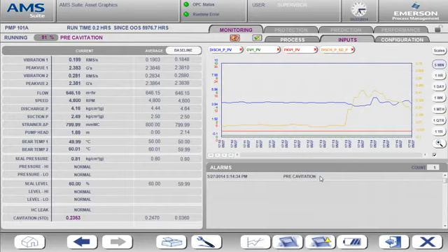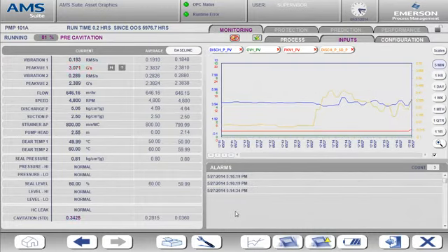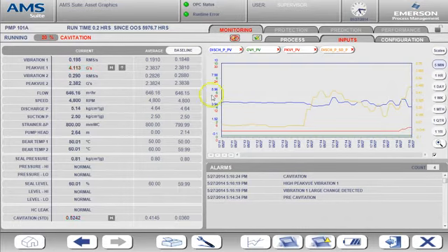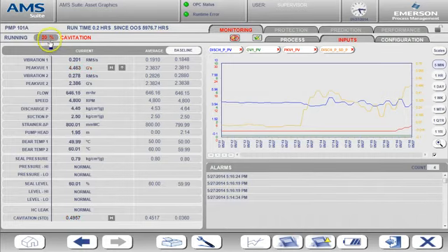At this point, none of the vibration inputs are high. Let's now look at the conditions that cause the cavitation alert to be active. Keep an eye on the vibration measurements on the trend. You'll see that the PeakVue value is increasing and is now high. Now look at the health value and alarm. We are now showing 20% health and a critical alert for cavitation.